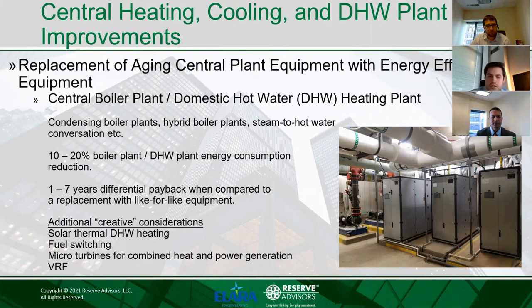Common options here include higher efficiency condensing boilers, hybrid boiler plants with condensing and non-condensing boilers, and also steam to hot water conversion. I won't be getting too much into technical details, but these are basically types of systems that can potentially provide higher energy efficiency. And with these types of projects, we typically see 10 to 20% energy consumption reduction with 1 to 7 years differential payback when compared to replacement with standard efficiency equipment.